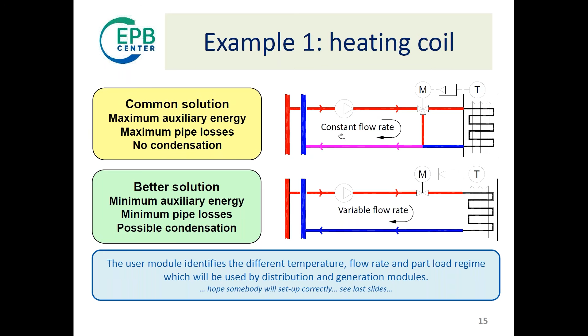This can be easily identified with these calculation modules, and it makes a difference when calculating the performance of your system. For example, you might think floor heating is ideal for a condensing boiler, but if you look carefully, you'll notice sometimes there's a mixing valve, so you have a reduced flow rate and a high delta T. Several boilers have a minimum flow rate, and again you get mixing. But if your boiler controls the primary pump, you may reduce the flow rate and restore low temperature to the boiler, so you're really condensing.